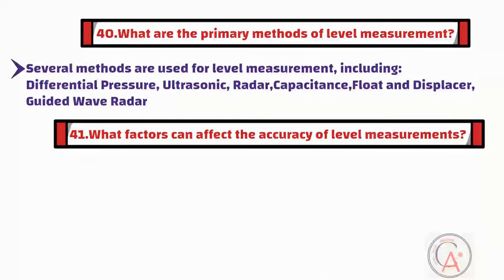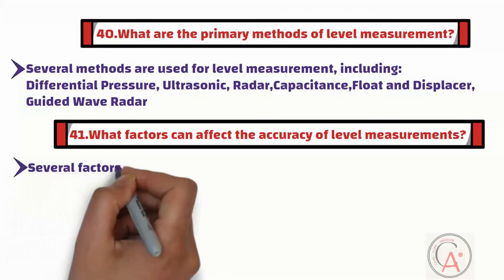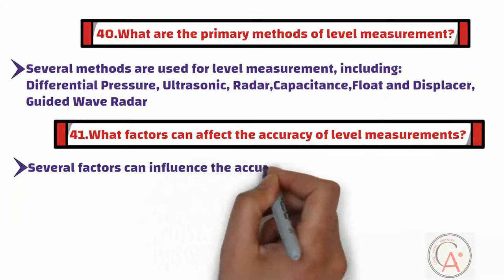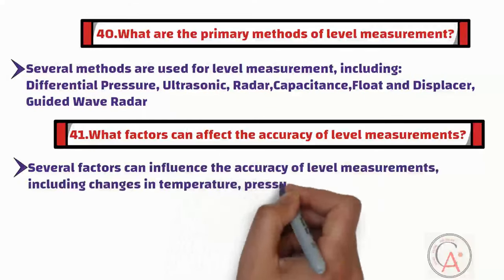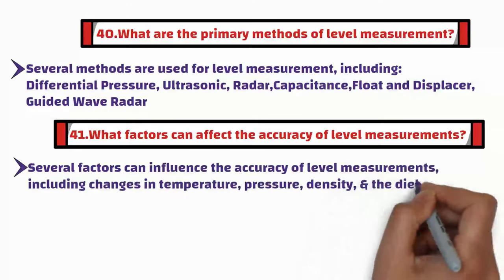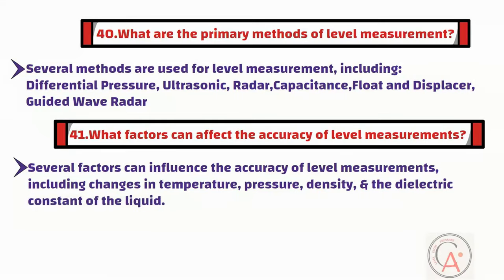Question forty-one is: what factors can affect the accuracy of level measurements? Several factors can influence the accuracy of level measurements, including changes in temperature, pressure, density, and the dielectric constant of the liquid. The vessel's geometry and the presence of foam or turbulence can also affect measurement accuracy.